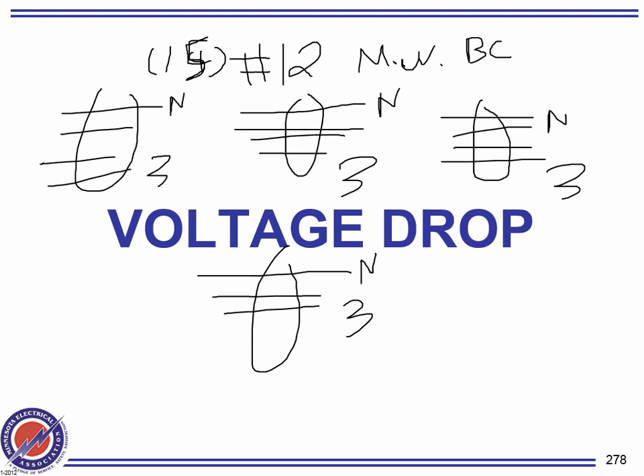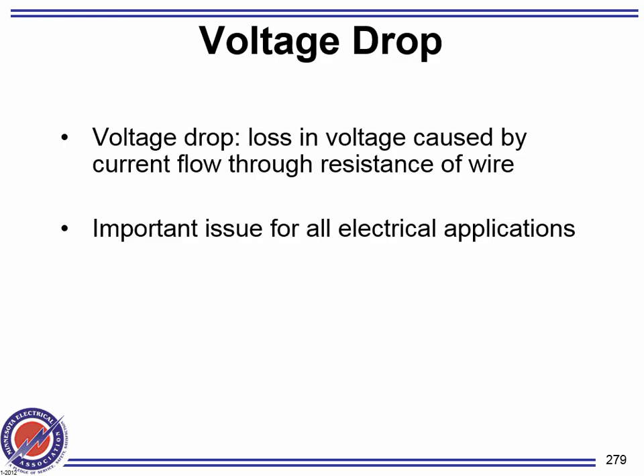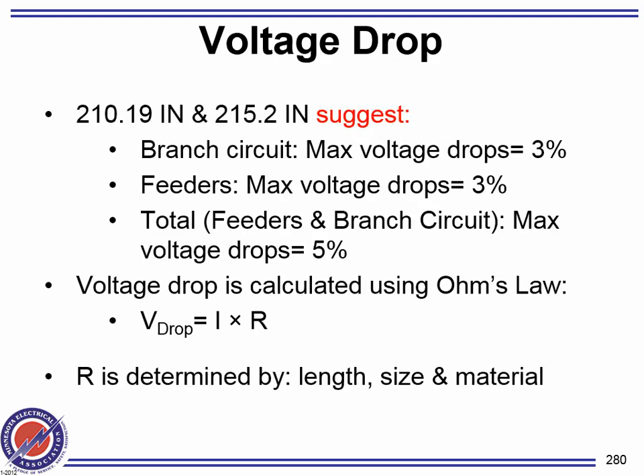They'll tell you that. So okay, voltage drop. Voltage drop, guys, is a requirement of, believe it or not, the building code, because it's part of the energy code in Minnesota. Voltage drop is required by the energy code in commercial buildings. You take 3%. In the NEC code book it is a suggestion, believe it or not. But in the building code, it's a requirement when we design a system.